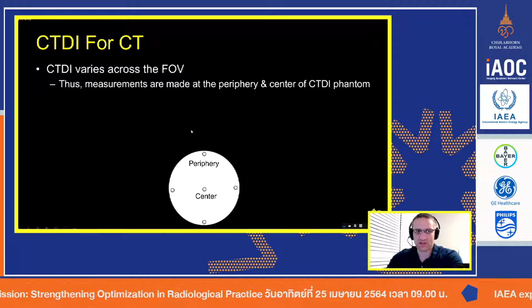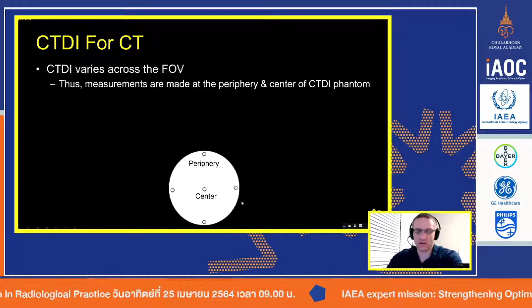All right, so the next thing to consider is when we make our dose calculations to calculate CTDI, we're going to make some measurements at the center and along the periphery. We do this so that we can take into account the area difference. So we know that the dose isn't perfectly homogeneous. It's a little less at the center, and it's a little higher at the periphery.